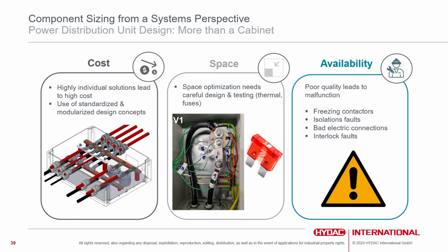We have made the experience that poor quality in the PDU, when there's no time and so on, really leads to malfunction in operation, and maybe also to late malfunctions. Like we have problems with freezing contactors, with moisture and freezing conditions, and contactors are freezing, and switching on is not possible anymore.